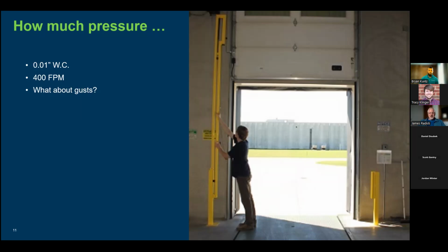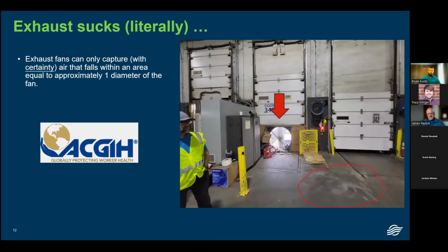So again, low pressure, hundredths of an inch water column, we found that's just enough pressure to turn and stop infiltration. We're not really pushing any more air out than what would be coming in through the building leaking anyway. So that's a misperception that some people have, that you're blowing all that air out. No, we're simply taking it and pre-tempering it with our equipment and moving it towards those doors. So we stop that cold air infiltration where it is. And you gain a lot of benefits with it, which we'll go over next here, Brian, please.